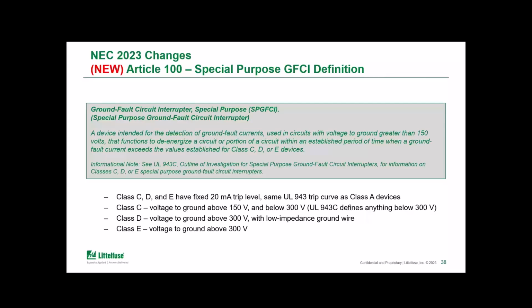And as shown, it states that it's intended for applications where voltage to ground is above 150 volts. And it does mention the Class C, D, and E devices according to the UL 943C document. So while it doesn't say it in the words there in the gray box, as we've talked about, these devices do follow the same trip curve as the Class A device, but they do have that 20 milliamp pickup level.